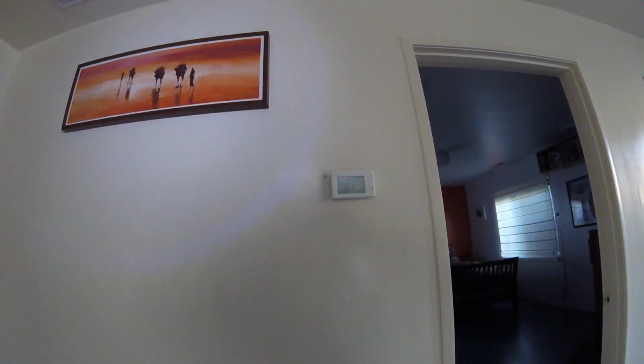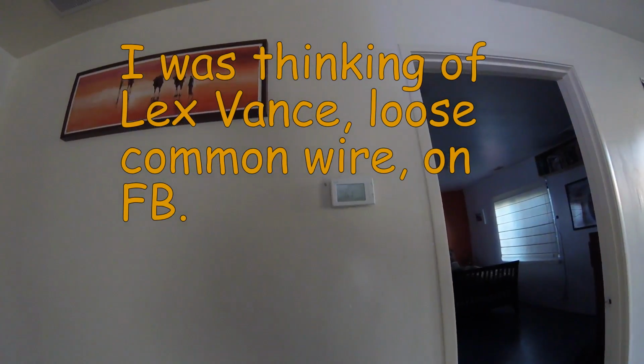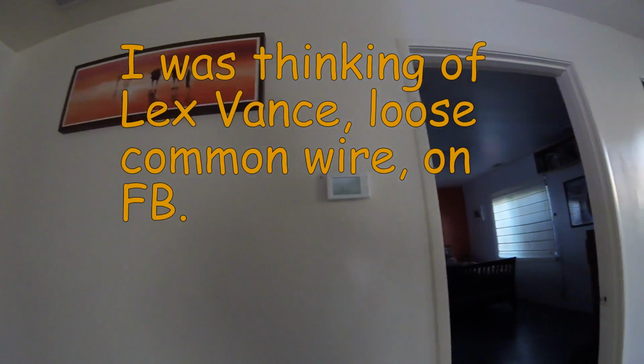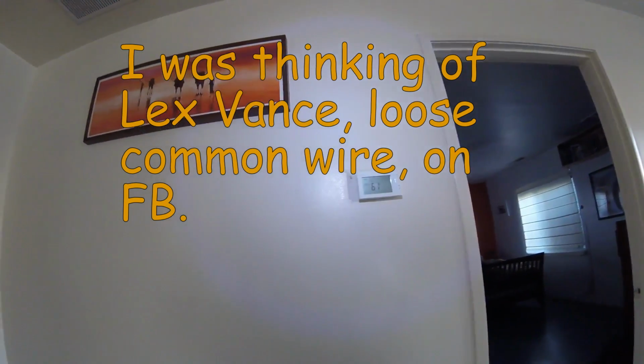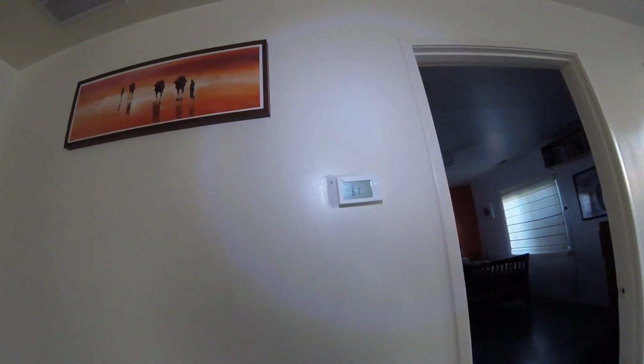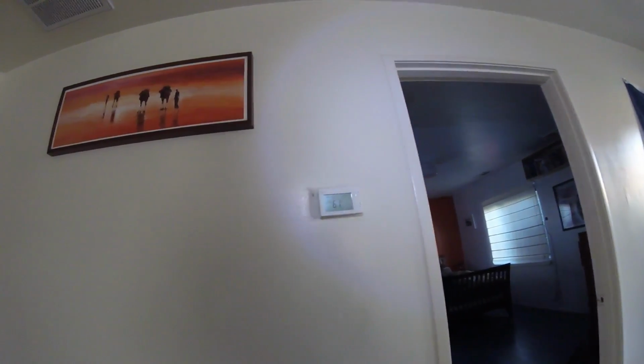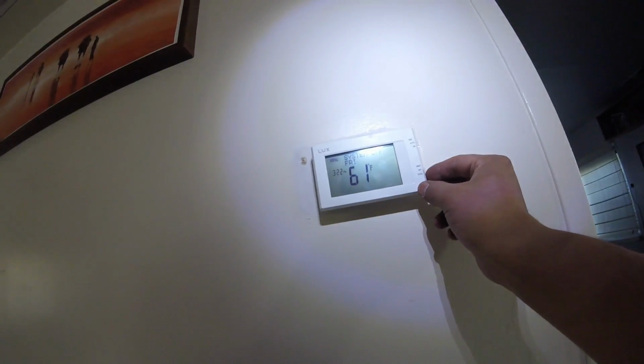Man, I remember yesterday I heard that guy mention on Facebook that his common wire was loose. This is kind of similar. I accidentally installed a bad transformer. And the first one popped because the wiring was wrong from the thermostat to the air handler. So here we go. Gotta try it on heat mode.